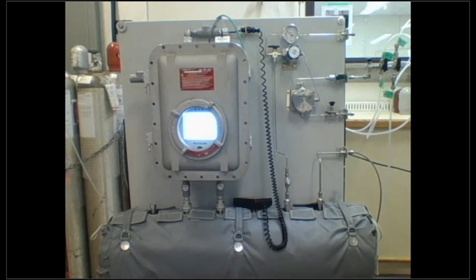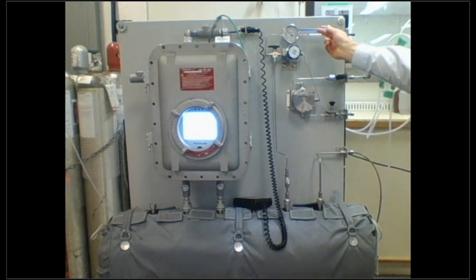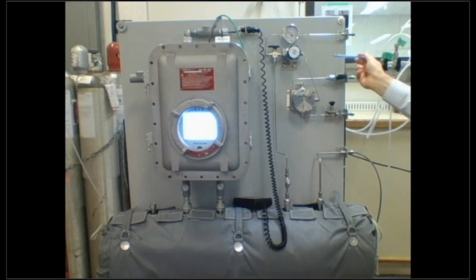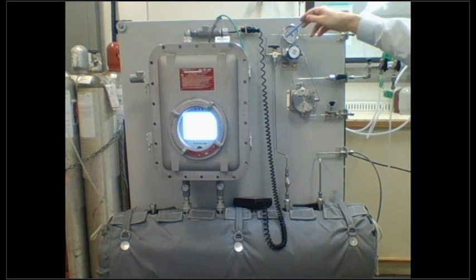So physically, a few things to point out. Along the side here, the gas entries are here. So we have the sample gas that's going through the membrane filter. We're using a Genie 123 membrane. There's an option for a fast loop here that you can use by opening the sweep from the Genie. That serves 2 purposes. One is to ensure that you have a representative sample at the analyzer at all times. Also, if any liquids fall out, they can be swept away. We go into a pressure regulator. We regulate the gas to 10 pounds per square inch gauge. There's a 3-way valve. In this case, it's a manual valve that can be used to introduce calibration gas. Optionally, we can have a solenoid valve to do that same function.